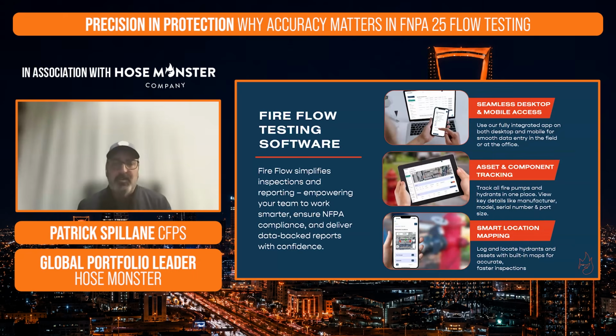And then we have our Fireflow testing software. This works with or without Smart Monsters. This is a standalone product, but when powered by Smart Monsters, it's going to improve the accuracy of our tests. Our Fireflow testing software has desktop and mobile access, so we can access it through our Smart Monster app, or we can log in through any desktop. But here's where we're going to be able to track and document all of our flow tests. So whether we're doing a fire pump test or a fire hydrant test, all this data can be put into our software, compiled into a very accurate NFPA style report.